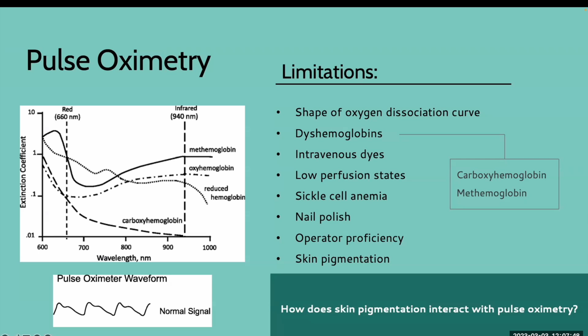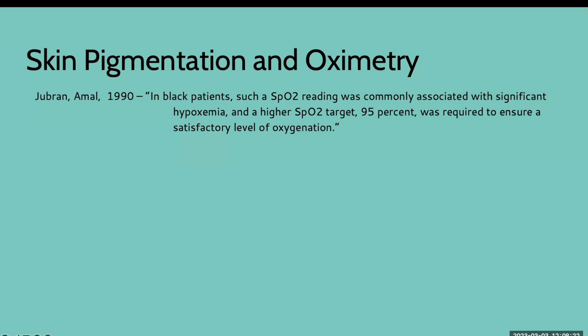So ever since modern pulse oximeters were deployed widely in the critical care setting, there have been concerns regarding its accuracy in Black patient populations. A 1990 study performed on mechanically ventilated patients found that for white patients, a pulse ox target of 92% was reliable in predicting satisfactory oxygenation. However, quote, in Black patients, such an SpO2 reading was commonly associated with significant hypoxemia, and a higher SpO2 target, 95%, was required to ensure a satisfactory level of oxygenation. 15 years later, in 2005, a UCSF study comparing 3 different pulse oximeter companies found that not only did dark skin pigmentation result in an overestimation of saturation, but that this overestimation was greater, especially at lower saturations, across the 3 tested devices.